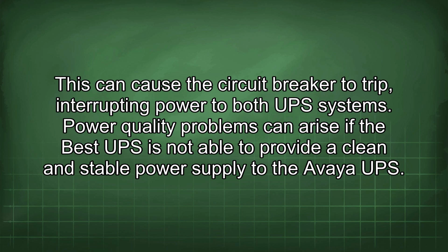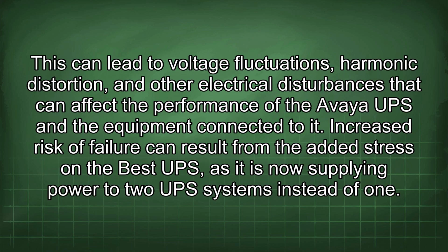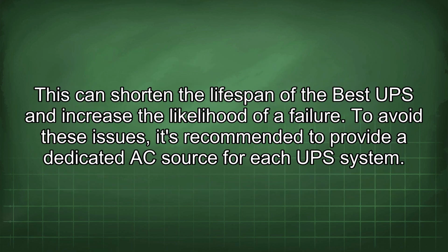Power quality problems can arise if the BEST UPS is not able to provide a clean and stable power supply to the Avaya UPS. This can lead to voltage fluctuations, harmonic distortion, and other electrical disturbances that can affect the performance of the Avaya UPS and the equipment connected to it. Increased risk of failure can result from the added stress on the BEST UPS, as it is now supplying power to two UPS systems instead of one. This can shorten the lifespan of the BEST UPS and increase the likelihood of a failure.